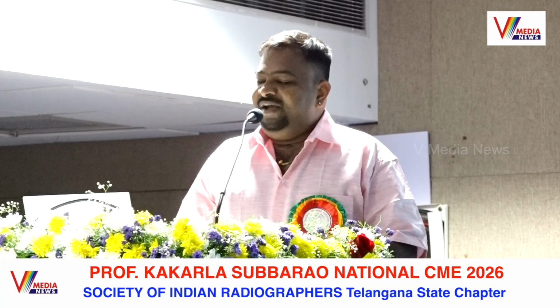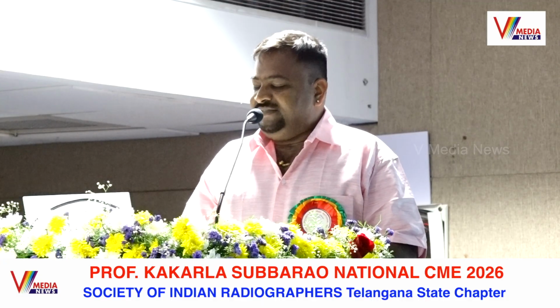What are the types of dual energy CT based on the sources and the detectors? We'll see one by one. First is the dual source, where we have two separate X-ray sources with two sets of detectors attached coaxially. The second option has only one X-ray tube and appropriately aligned detectors, but the kV switching happens in the same X-ray tube rapidly, which we call rapid kV switching.